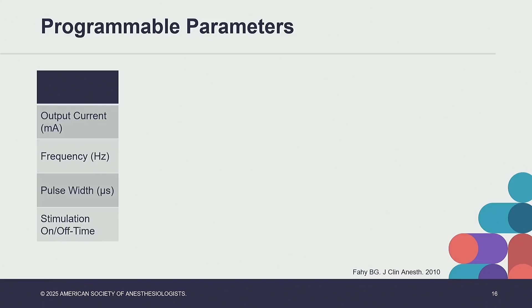The typical parameters for the treatment of seizures and depression are quite similar, with stimulation every 5 minutes that lasts for 30 seconds in duration. And then newer VNS models for epilepsy have an optional auto-stimulation mode, which senses tachycardia and delivers periods of continuous vagal nerve stimulation. The reason for this is that tachycardia is seen in 80% of patients while they're having a seizure, and thus with this auto-stimulation mode, it would be potentially able to prevent or abort a seizure if it were to occur.